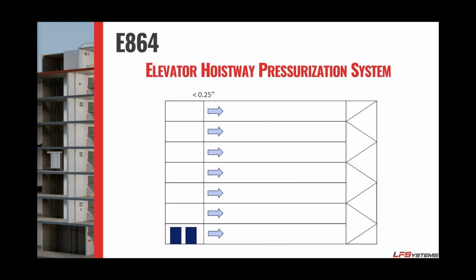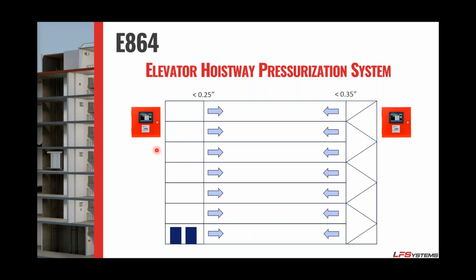So when we talk about why we do compensated systems, in a practical sense, if you are maintaining below 1/4 of an inch, that pressure will dissipate in your corridor. Now, if it's tied right next to your stairwells, that might affect it. However, if you start to exceed that 1/4 of an inch, you start to overpressurize your hoistways. It actually starts to push air and smoke toward your stairwells, and you can actually start to push smoke into your stairwell. So while the elevator hoistway controller does not necessarily directly talk to the stairwell controller, they do work in concert.